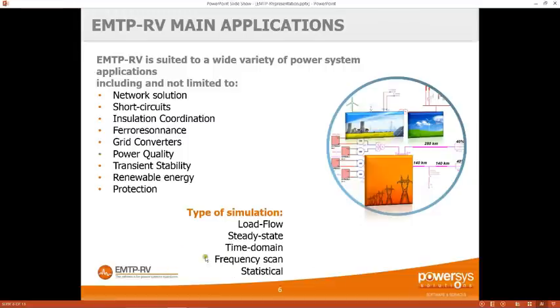There are two other convenient simulation types. The first is the frequency scan. You use this when, for example, you want to study the connection of a power plant to a network and the plant might inject harmonics. You do a frequency scan at the point of connection to identify all natural frequencies of the network. The output is the magnitude and angle of the impedance over a large frequency range, allowing you to identify poles and zeros and ensure injected harmonics are not close to them.